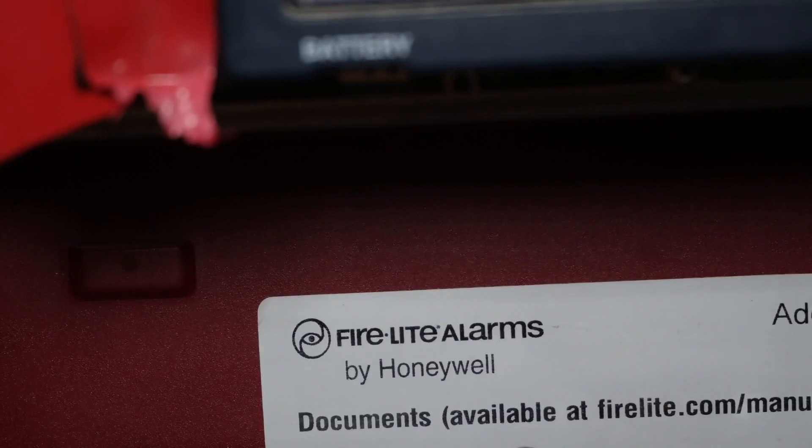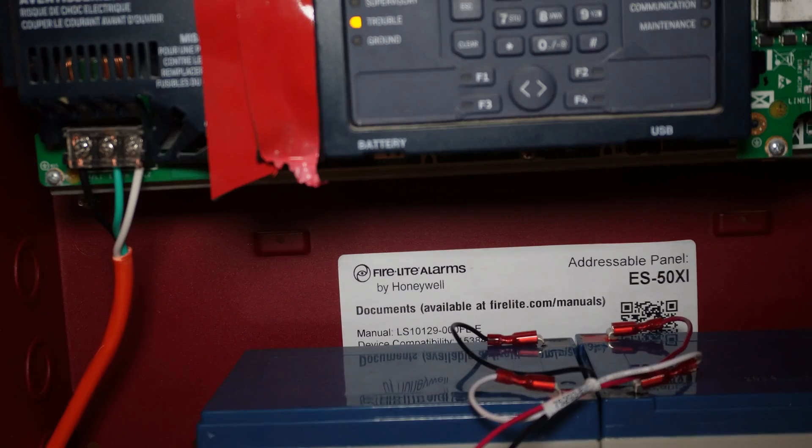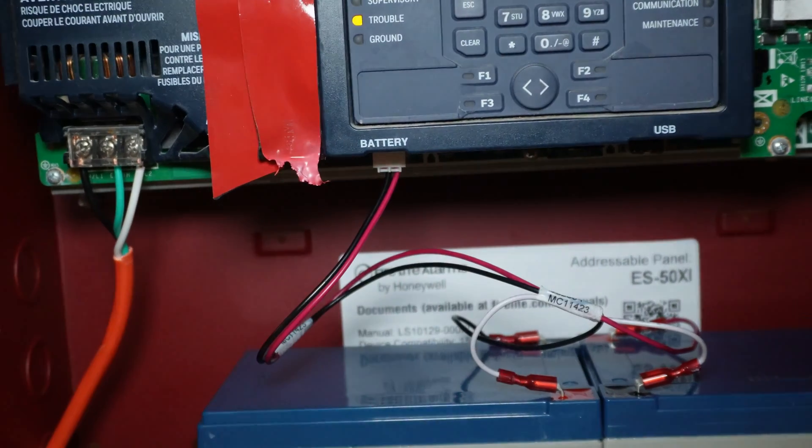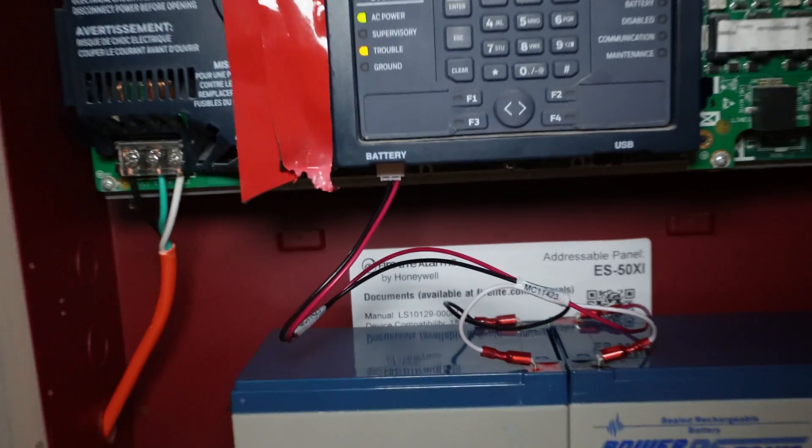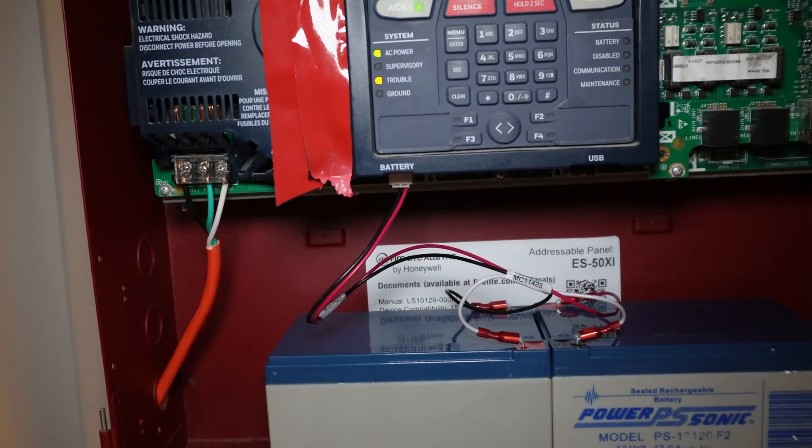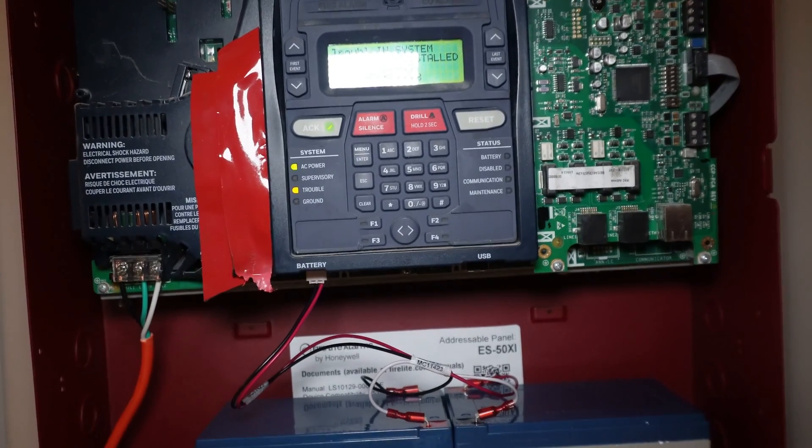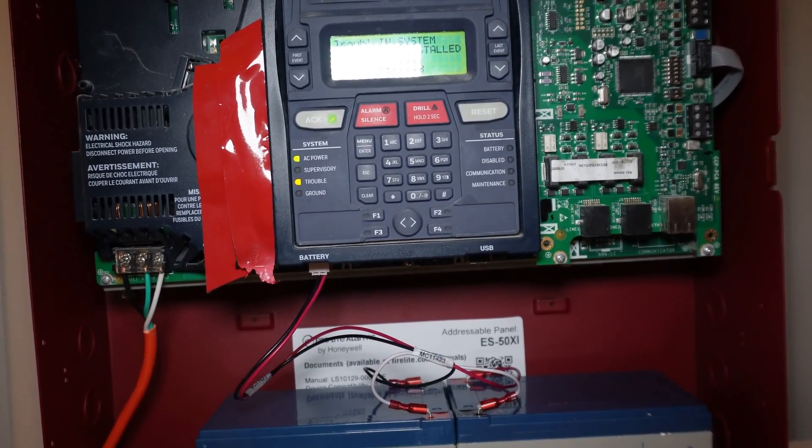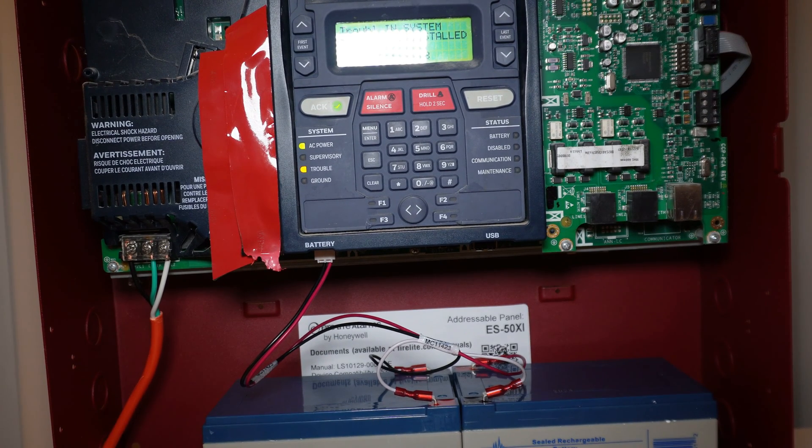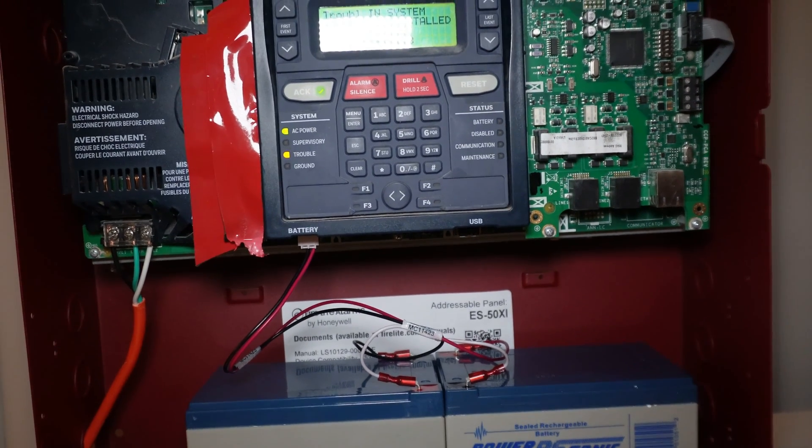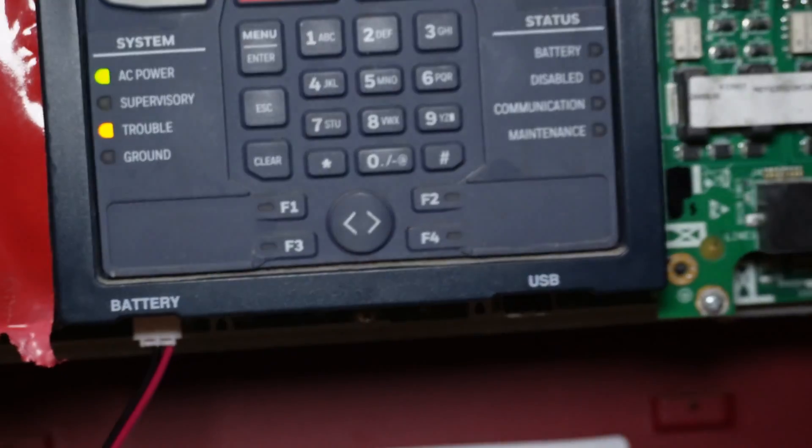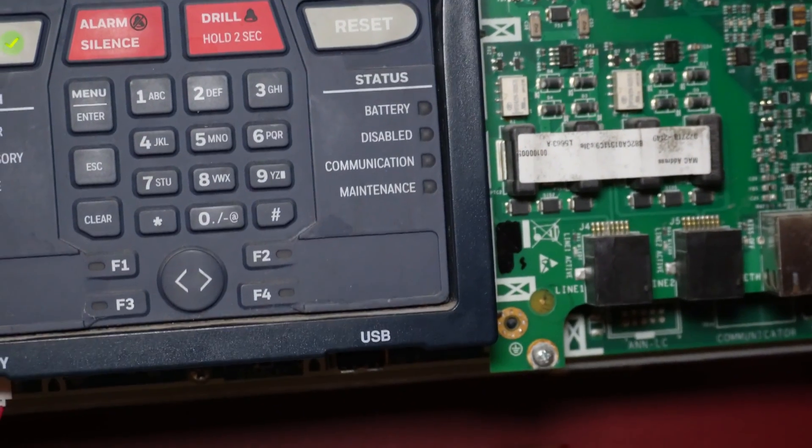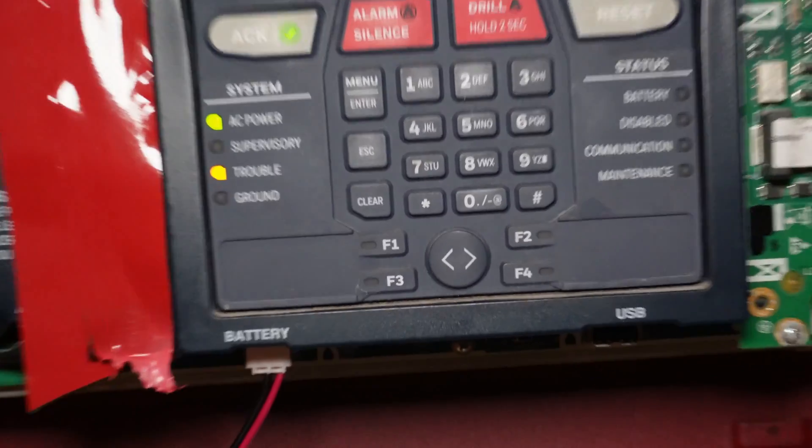All right, we have just installed the fire alarm control panel batteries. If you've been paying attention to the warning lights over here, you'll notice that battery is no longer lit up, so it's no longer having trouble with the battery.